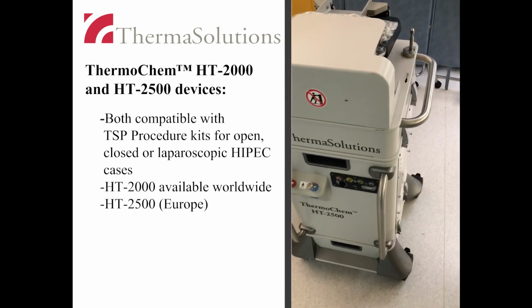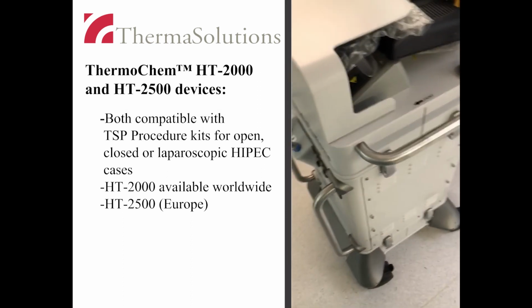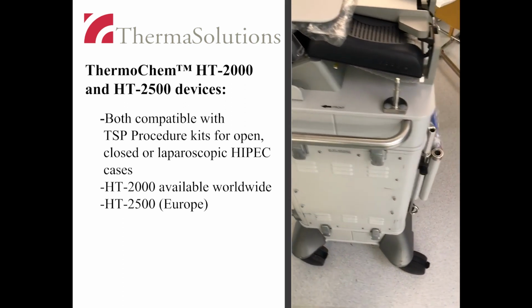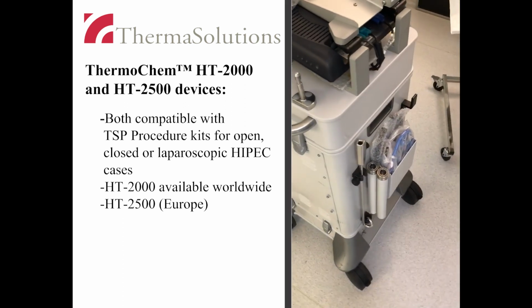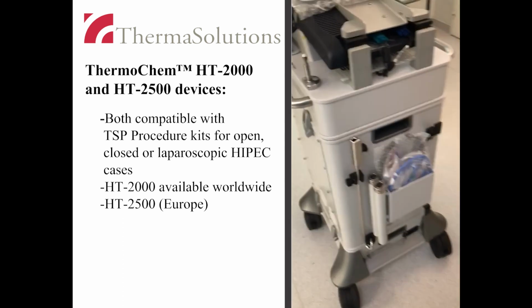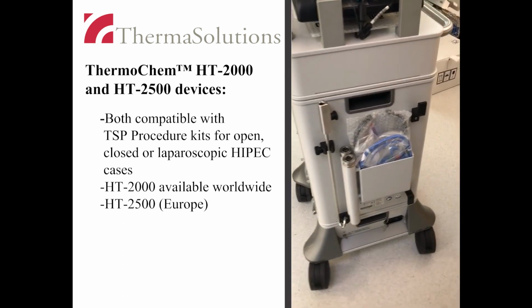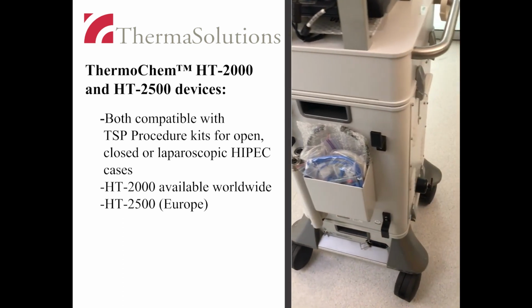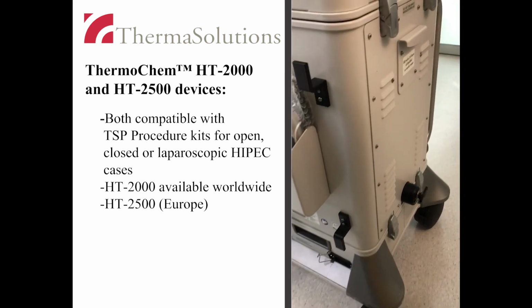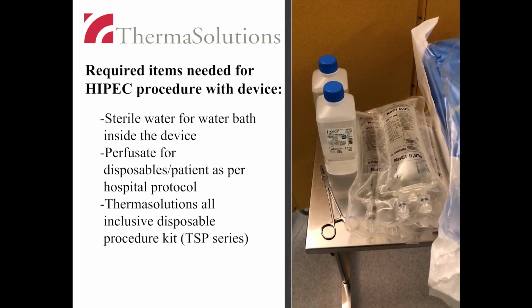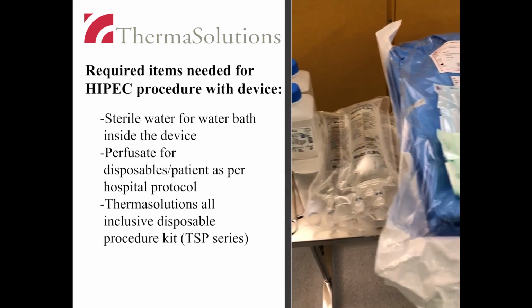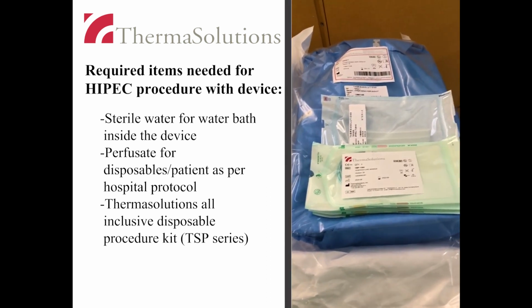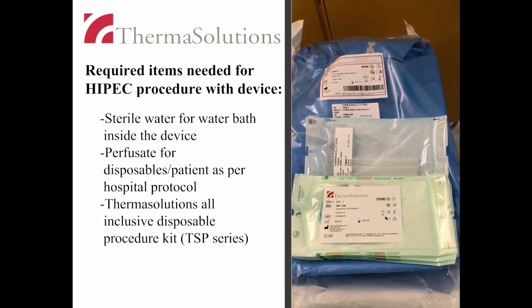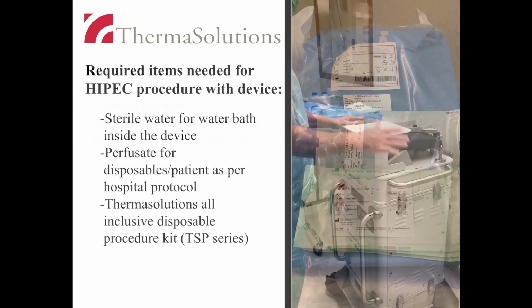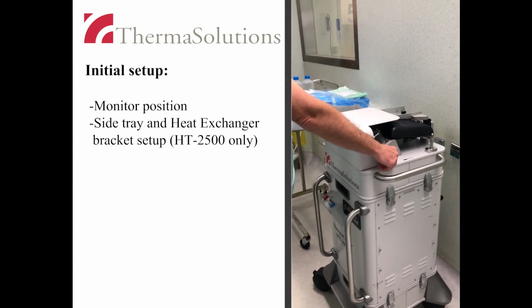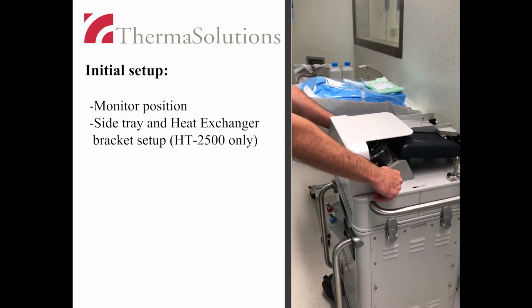The ThermoChem HT-2000 and HT-2500 devices are both compatible with TSP Procedure Kits and can be used for open, closed, or laparoscopic HIPEC cases. The HT-2000 is available worldwide and the HT-2500 is available in Europe. Additional required items needed for the HIPEC procedure include sterile water for the device water bath, perfusate bags, and the all-inclusive TSP procedure kit. If the device has been in storage, some setup may be required.